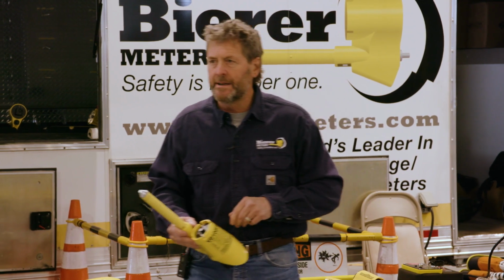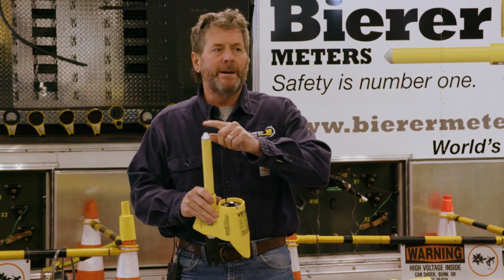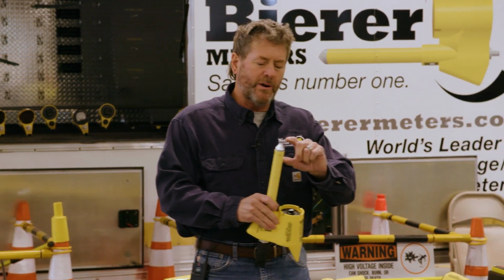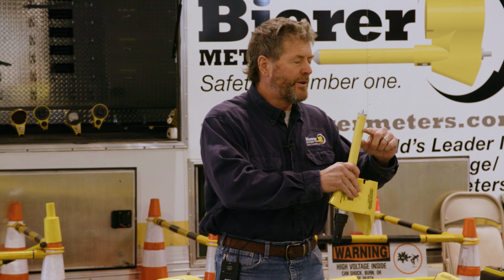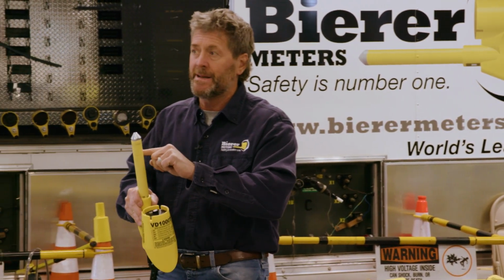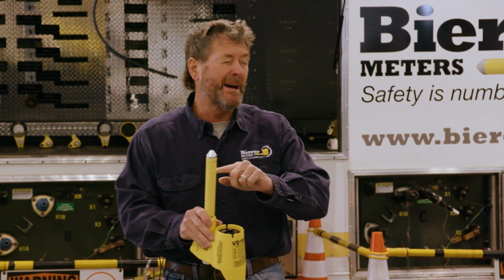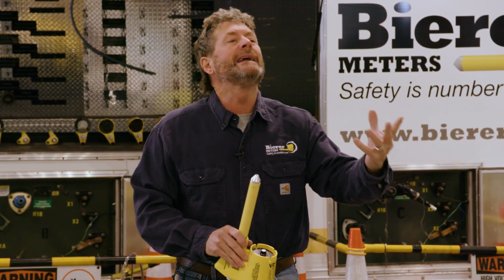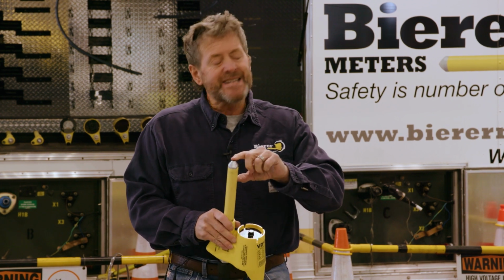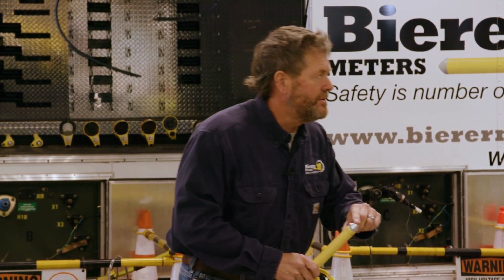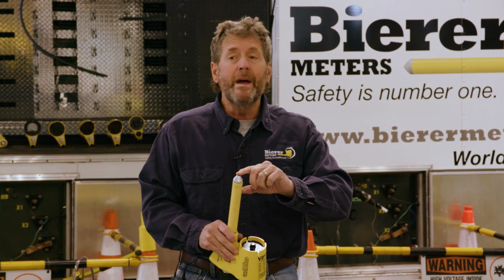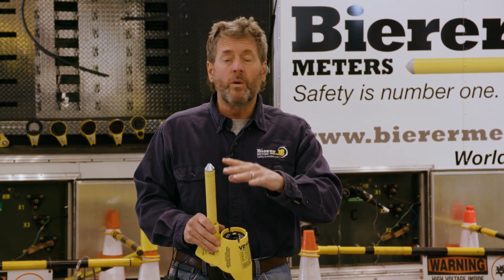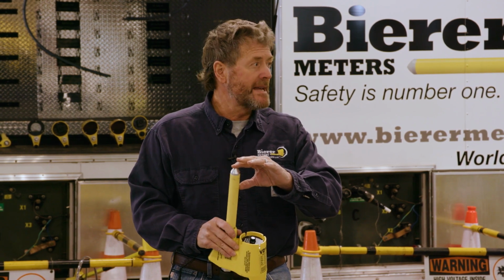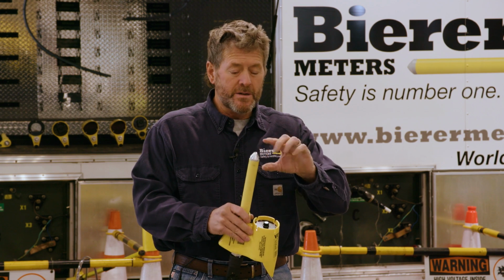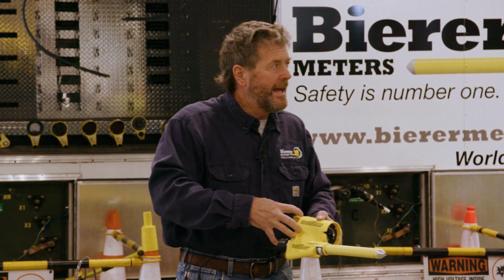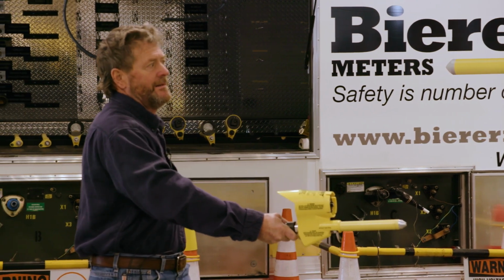All right, so how is it energized? Right here, you're touching primary at the tip of the tool. You're touching primary, we have resistors, there's a line limit here. If you look at your PD800W carefully, there's a line limit about 2.5 inches down. ASTM has required it since about 2009. That's just to remind you, okay, that's where the resistors are, and it reminds you not to bypass the resistors with a ground plane or with another hot phase. Does that make sense? Because this is your protection, so the resistors here protect the tool and also protect you behind the tool.